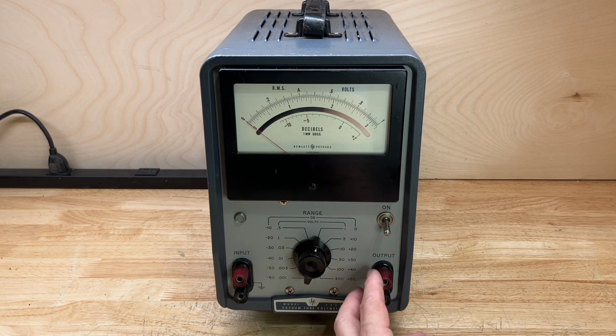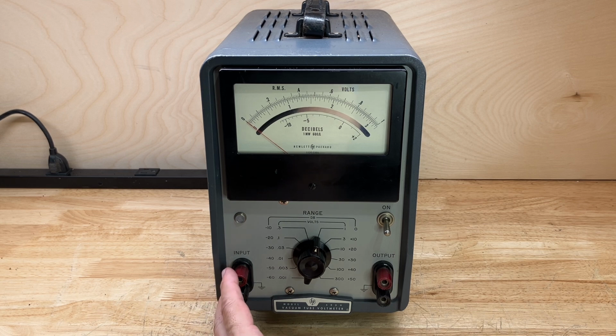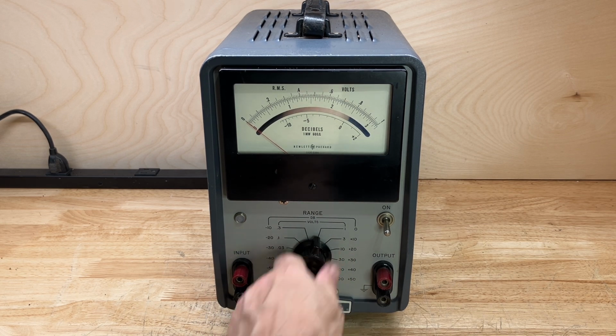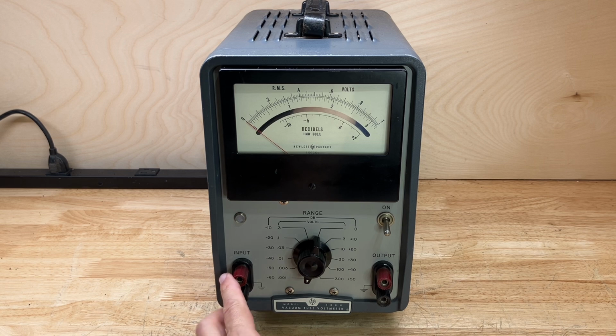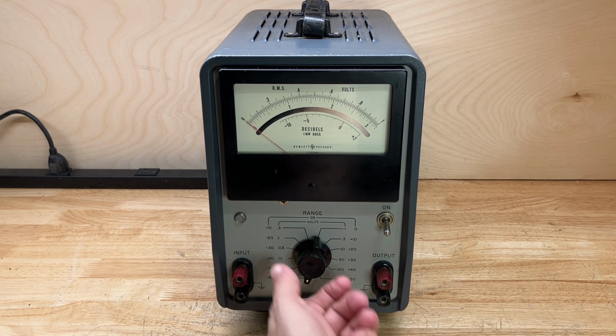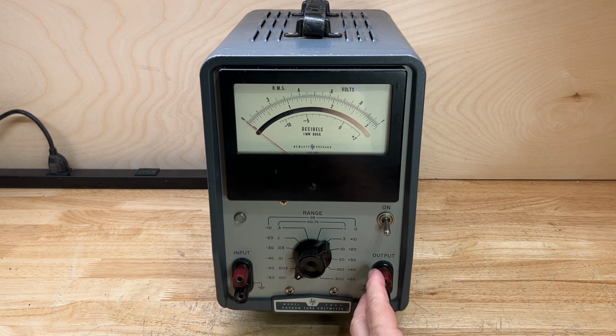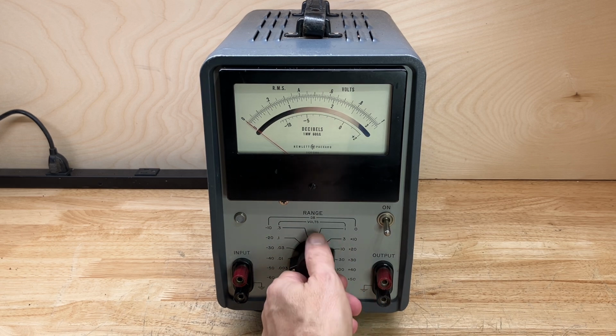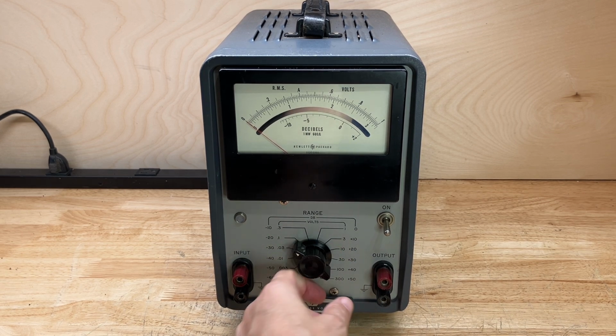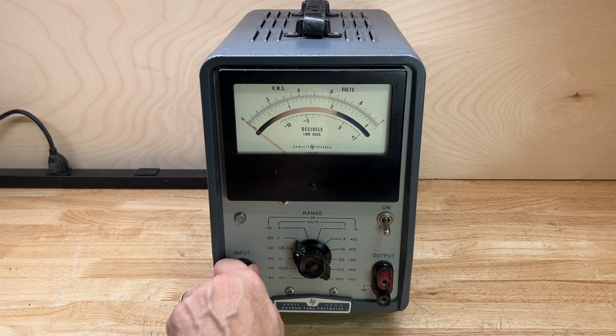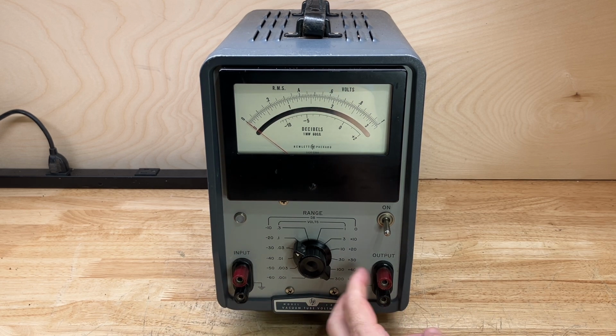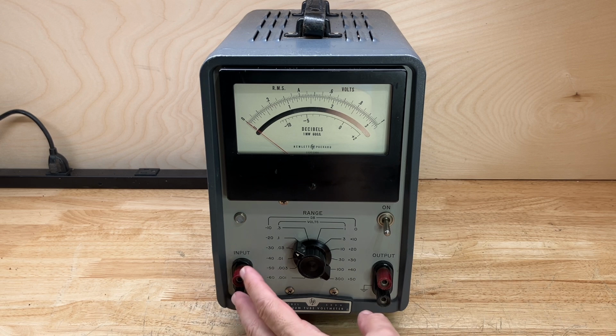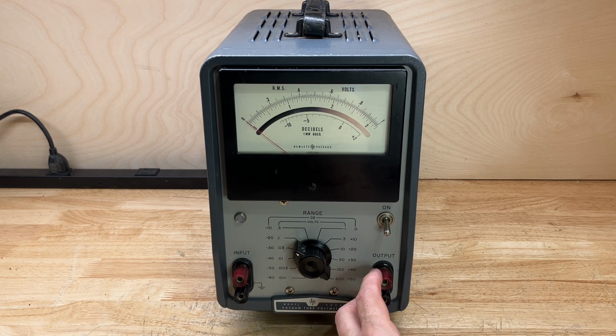It also has an output jack here that outputs 150 millivolts RMS AC for full scale input. So if you have it set to the 1 millivolt range, it has a gain of 150. Set to the 3 millivolt range, it has a gain of 50. 15, 5, 1.5 - so you get the idea. So that 150 millivolt AC output can be used as an amplifier.